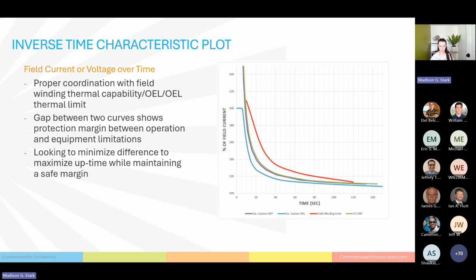Perfect. This is our overexcitation limiter. Great. And then the next thing we hit is our phase relays. Fantastic. And then the next thing we hit is our field winding limit. So the field winding limit is a little different than the overall thermal limit of the generator, but this is an acceptable coordination metric for a synchronous generator coordination. So one thing this also accounts for that you don't see on the power plot is time. So as time increases, even at a lower percent of field current, you're still going to hit those limits and those trips. So it is time protected for lower deviations, but those require a lot longer for the system to trip.